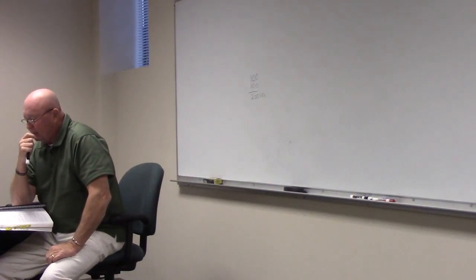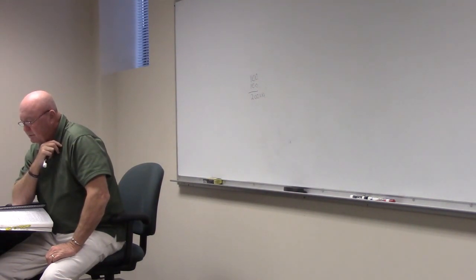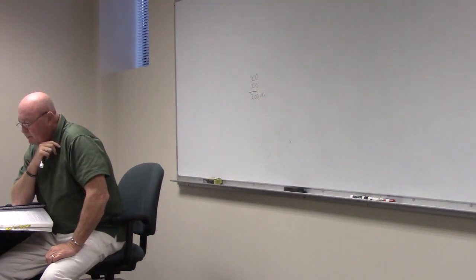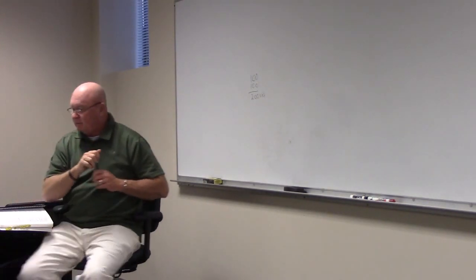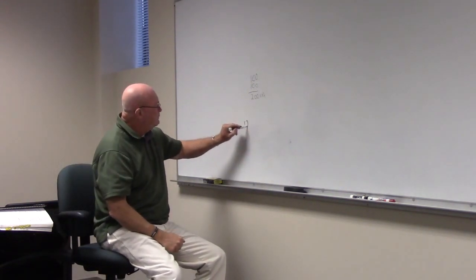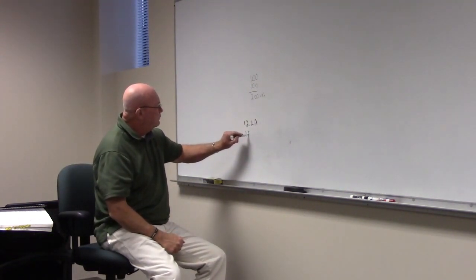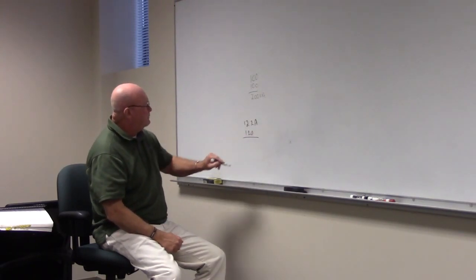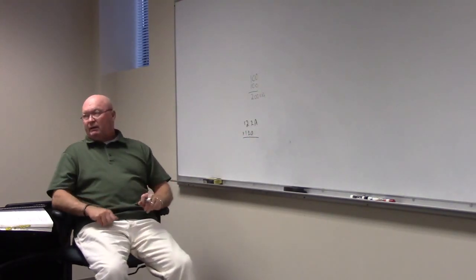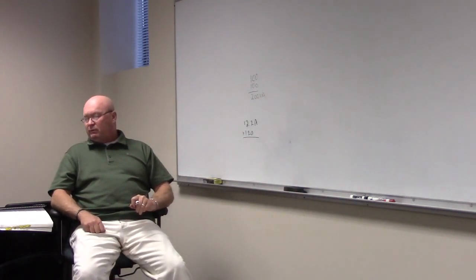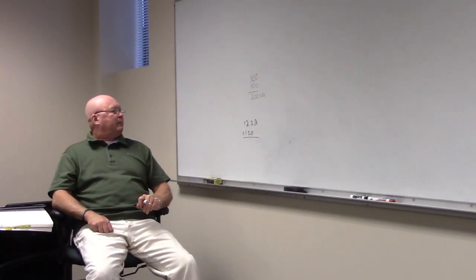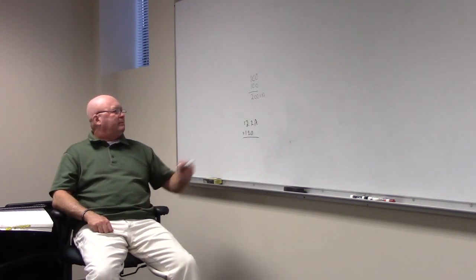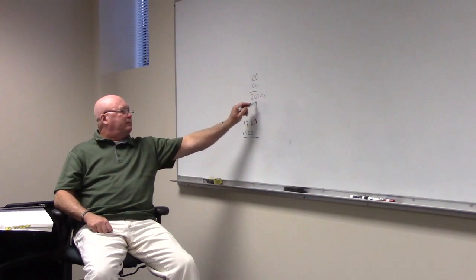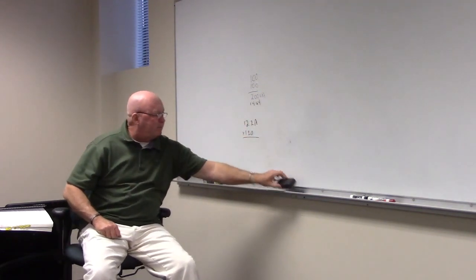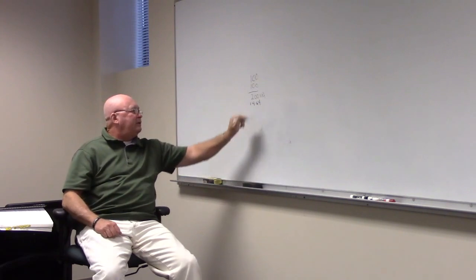Determine the remaining loads. The only other electrical outlet in the stand consists of 2 receptacles. One furnishes power for a refrigerator, and it's 12.2 amps. It's 12.2 amps, and it's 120 volts. So what we've got to do is get the volt-amps on this. So we're going to multiply these two out, and what do we get? 12.2 times 120 volts. 1,464 VA. Yep, that's a refrigerator. We've got to add that to it.